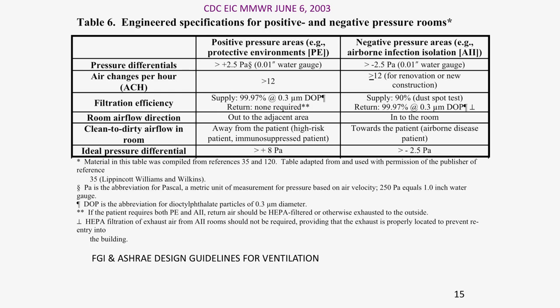So when you think about what we need to do, especially for ventilation, we need to think about what the specifications are. What kind of pressure relationships should we have? What kind of air changes per hour in the special ventilation rooms, or the filtration efficacy, either in the positive pressure protected environments, or the negative pressure airborne infection isolation requirements, where we want to contain the diseased individual.